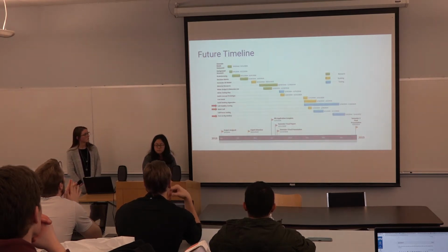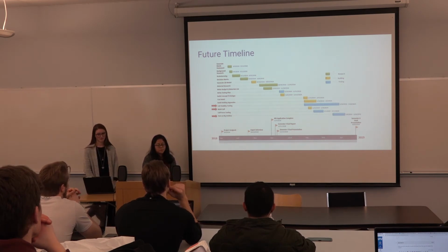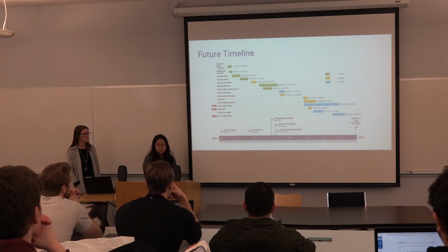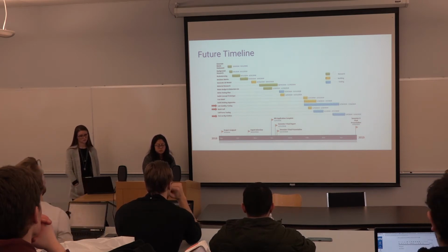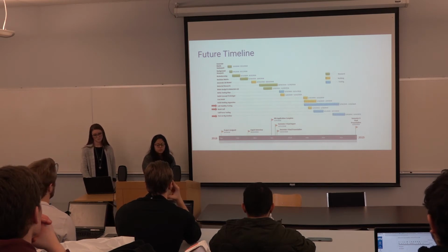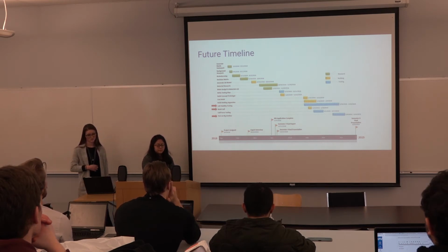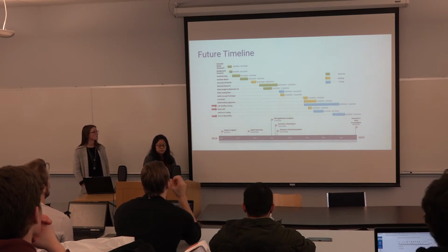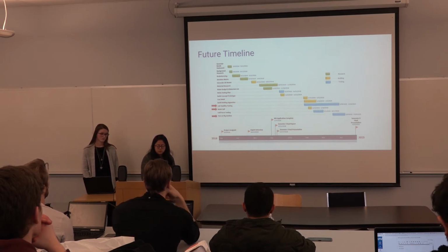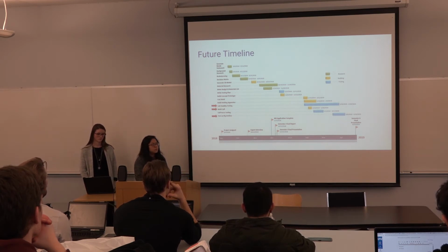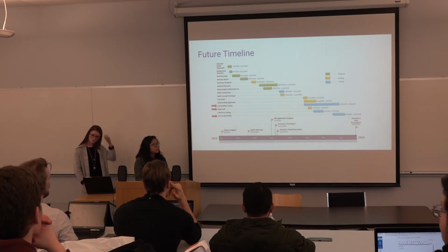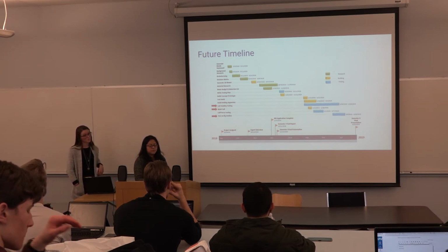In the future, we plan on fabricating our cuff via injection molding, as well as comparing the biocompatibility of a variety of different materials, such as PDMS or different liquid silicone rubbers. We plan on doing this by performing some cell viability assays, as well as comparing the surfaces of each material under the SEM microscope. We also plan on testing the material durability on a pig urinary system. We're planning on performing approximately 1,000 cycles on the pig, which we're going to obtain from a local slaughterhouse.